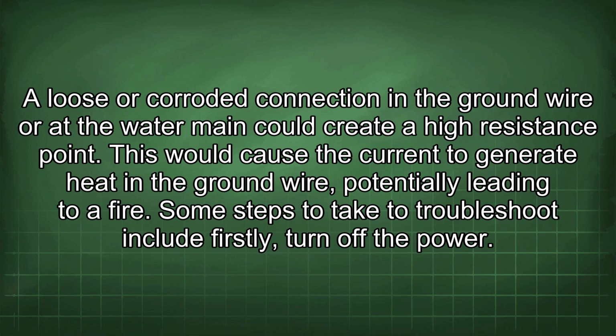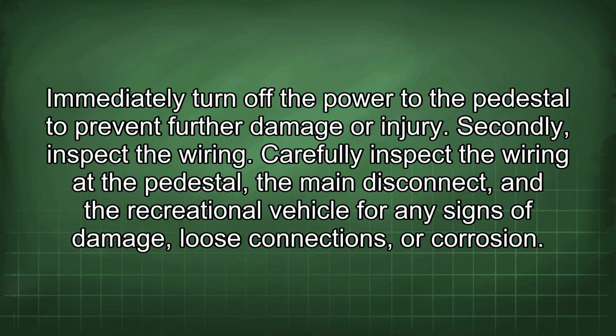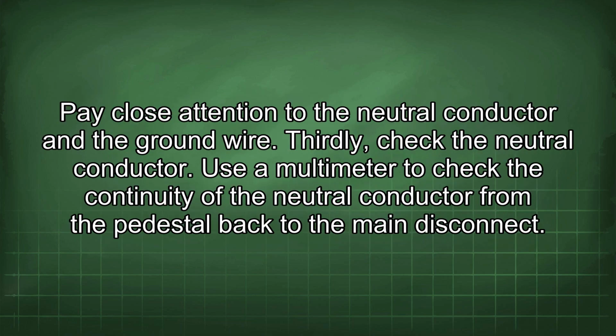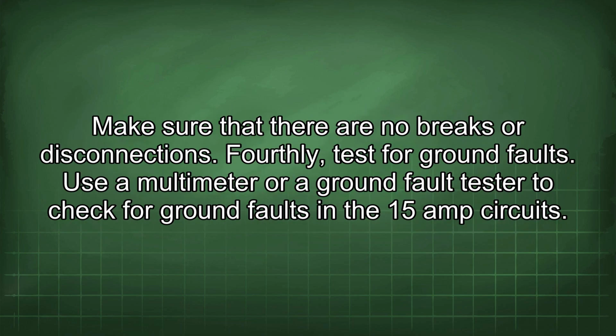Some steps to take to troubleshoot include, firstly, turn off the power. Immediately turn off the power to the pedestal to prevent further damage or injury. Secondly, inspect the wiring. Carefully inspect the wiring at the pedestal, the main disconnect, and the recreational vehicle for any signs of damage, loose connections, or corrosion. Pay close attention to the neutral conductor and the ground wire. Thirdly, check the neutral conductor. Use a multimeter to check the continuity of the neutral conductor from the pedestal back to the main disconnect. Make sure that there are no breaks or disconnections.